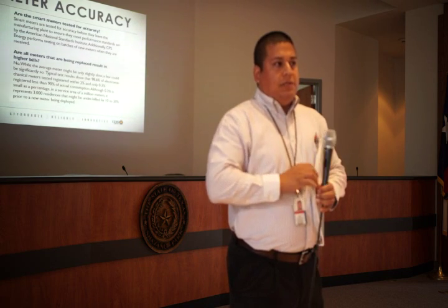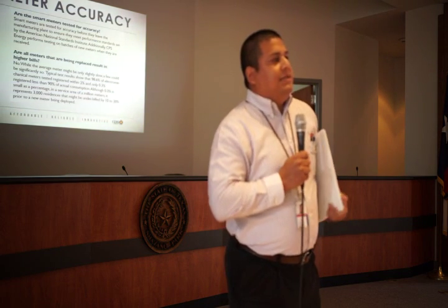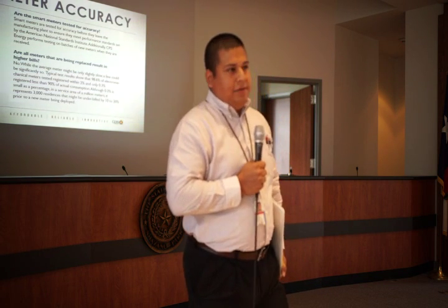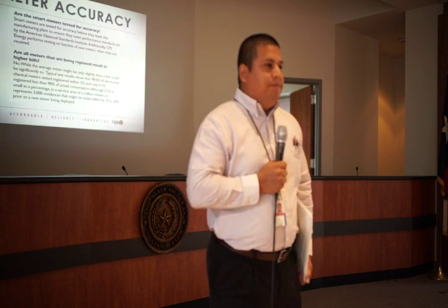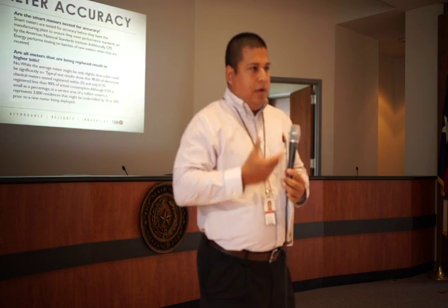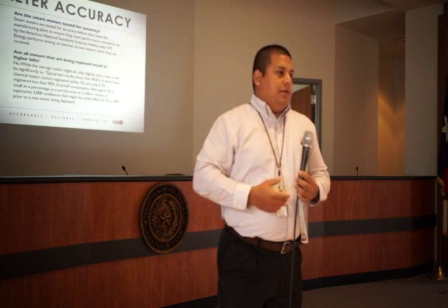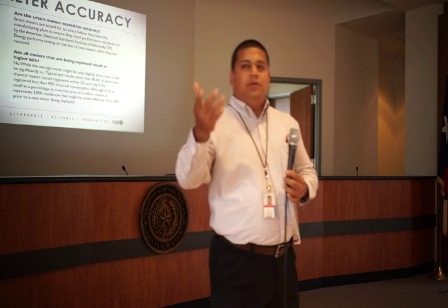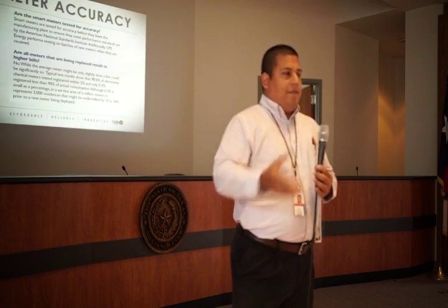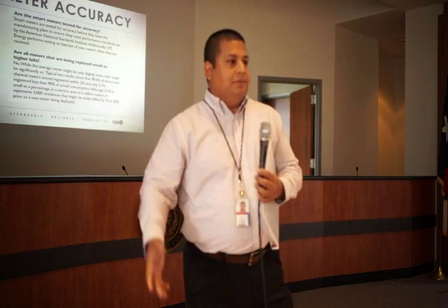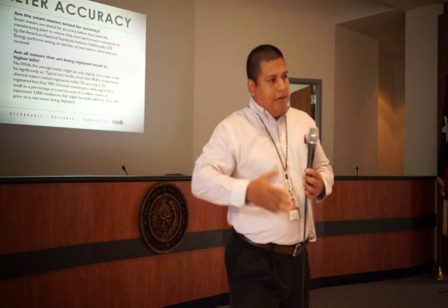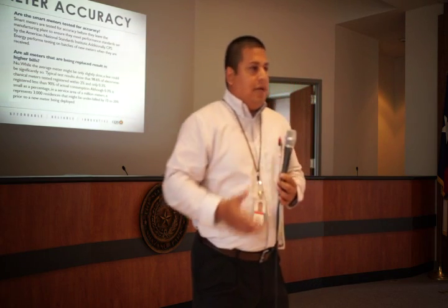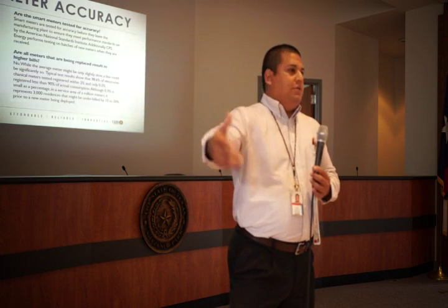So the way the testing works is CPS actually has a standards laboratory, and all our equipment is compared to a standard that's referenced back to the National Institute of Standards. What that does is guarantee that a watt hour is a watt hour, and every utility is held to the same reference, right? So the meter shop goes out to test the equipment, and we have equipment that tests the meters, and that equipment is traceable. We send that equipment back over to the NIST lab, and they calibrate it. It comes back to our lab. We calibrate our equipment that goes out to test the meters.